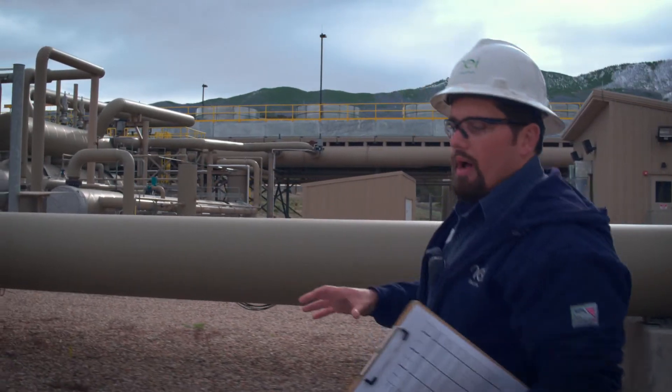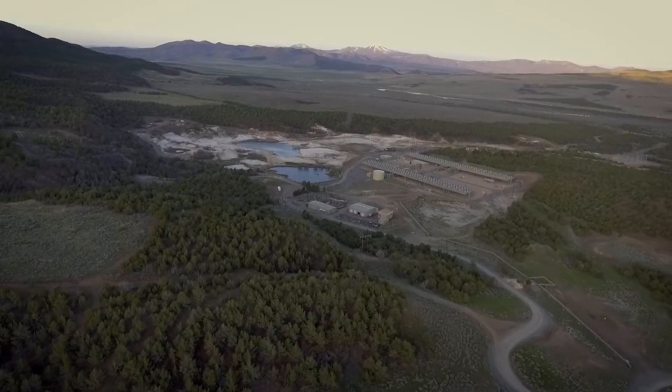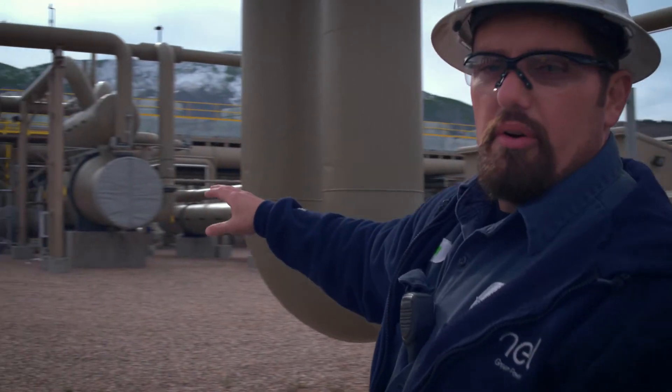That's what turns the geothermal brine into power. The Cove Fort geothermal plant uses geothermal fluid that we pump out of the ground in electrical submersible pumps. We pump that fluid through tube shell heat exchangers. We make sure that the brine stays pressurized and never actually turns to steam. So we use a motive fluid — it's isopentane. The pentane is superheated into a vapor and drives the turbines.